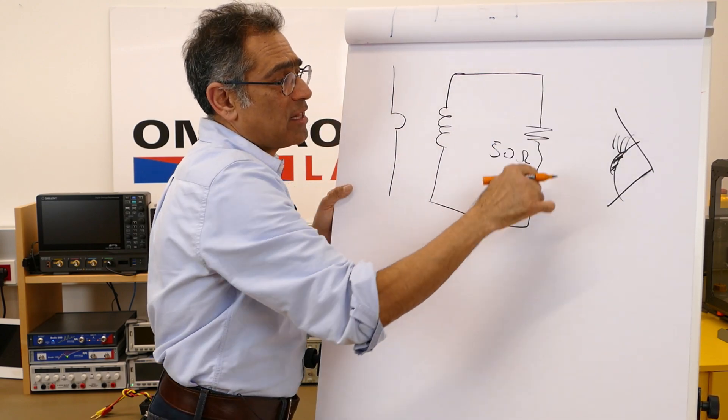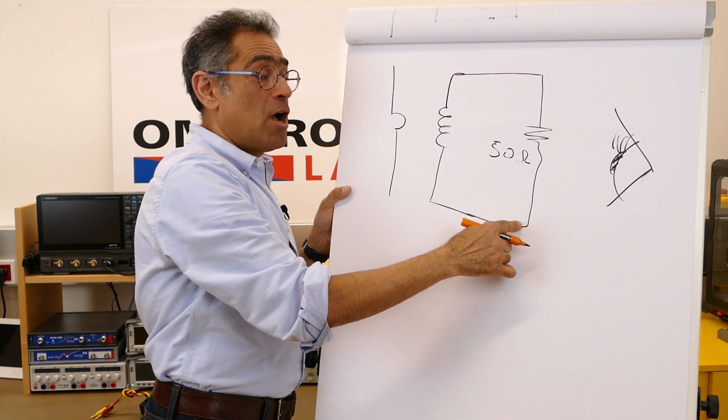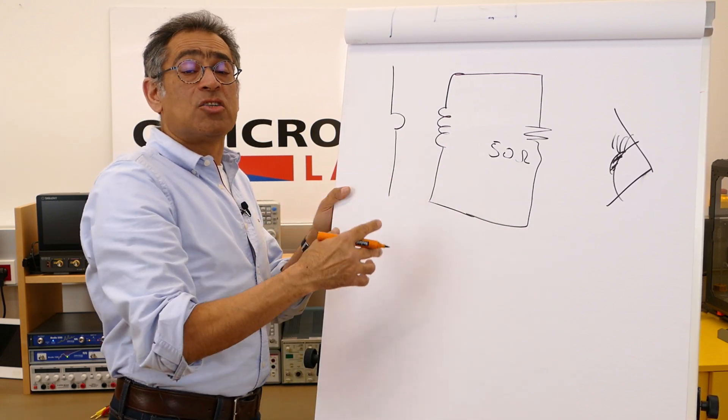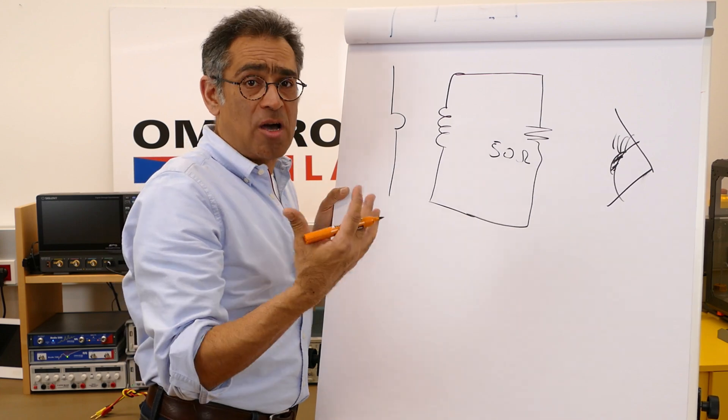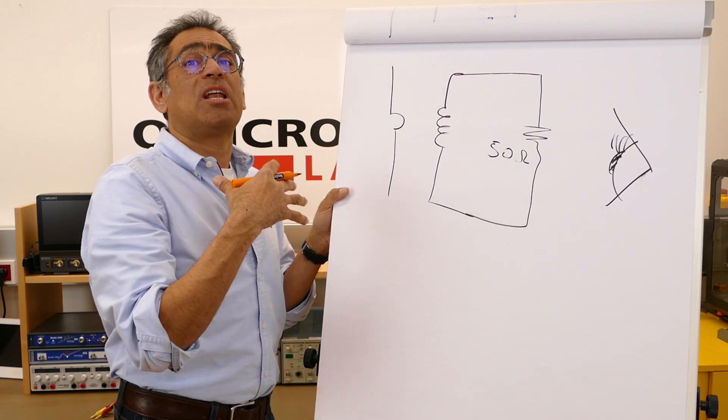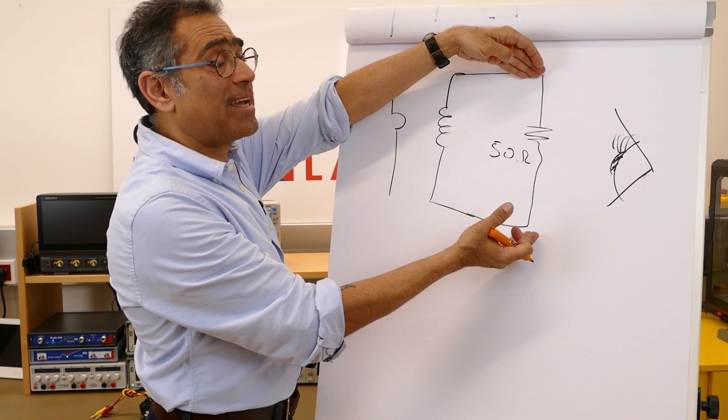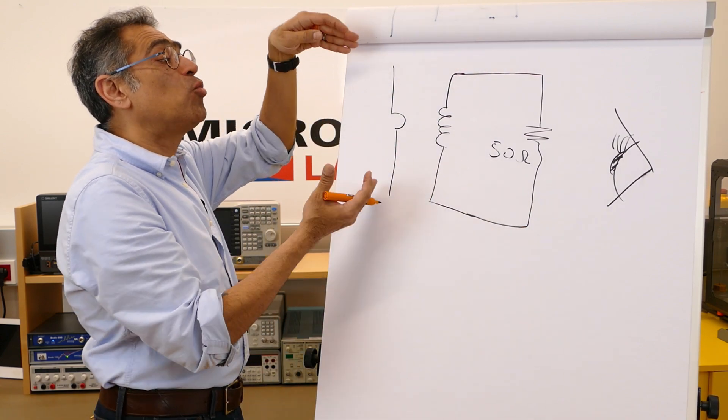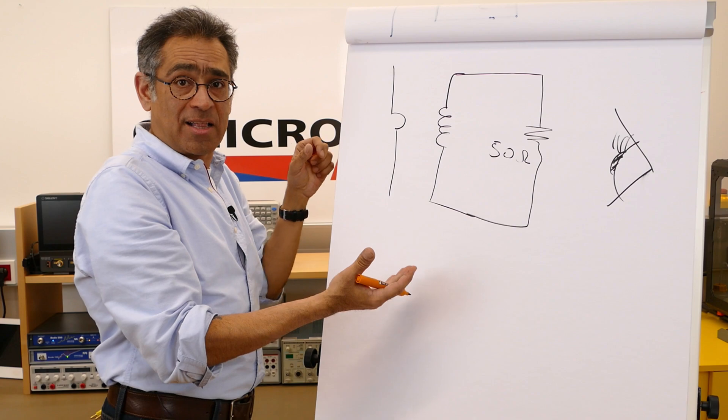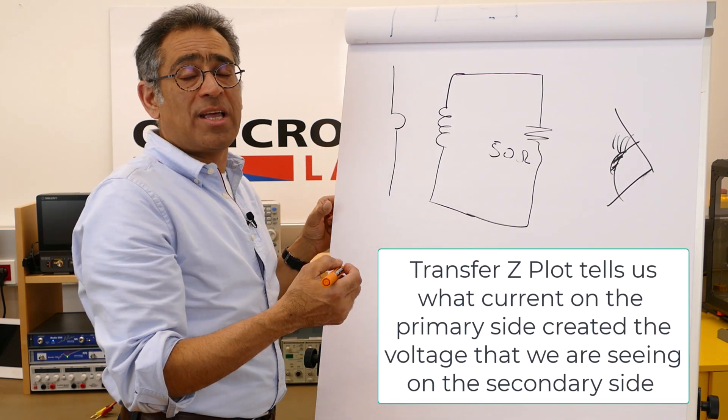But we are interested in the current on the primary, so effectively you need some kind of a translation table or some kind of a plot that takes the voltage on the secondary side and translates it into what was it on the primary side that created it, and that is called the transfer impedance.